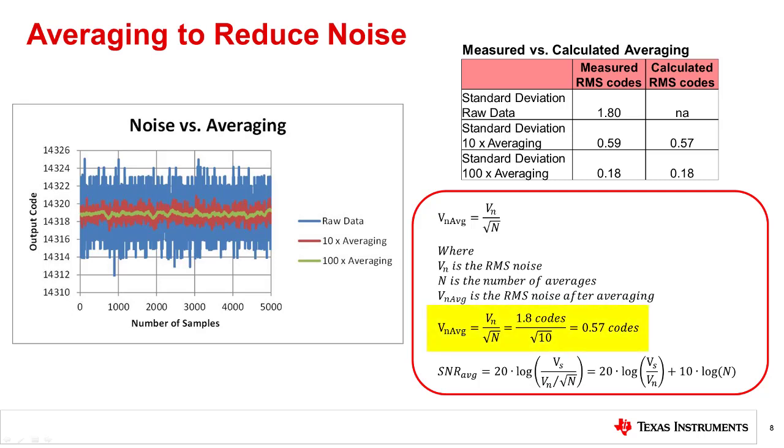The averaged noise is taking the 1.8 codes of un-averaged noise and dividing by the square root of 10, which yields 0.57 codes of RMS noise after averaging. A 10-point rolling average was done on the ADC data, and the standard deviation of the average data was calculated to be 0.59, so the effect of averaging on the actual measured data very closely matched the predicted noise by dividing by the square root of n. Then, a similar experiment was done with a 100-point rolling average, and both the calculated and measured average correspond quite well, reducing the noise to about 0.18 codes RMS.